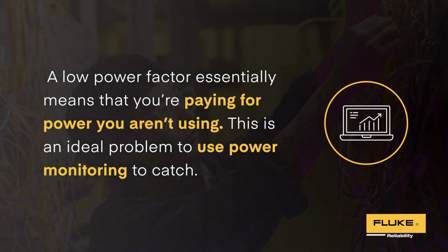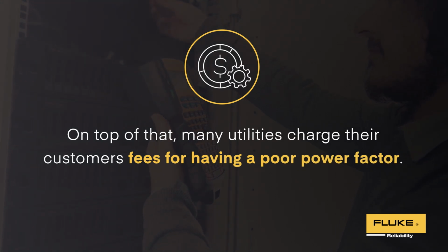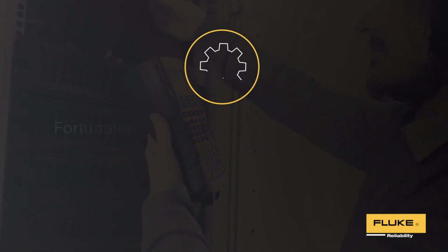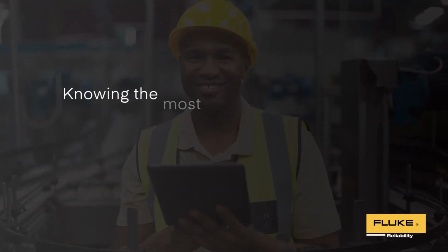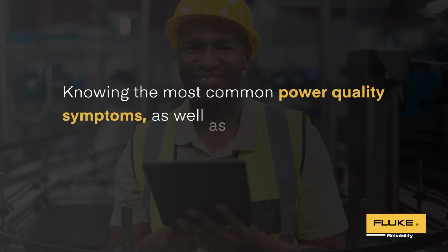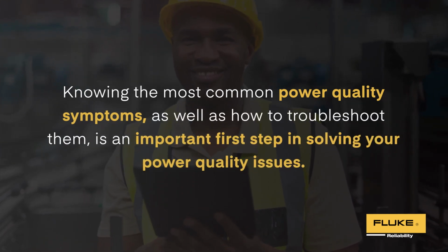This is an ideal problem to use power monitoring to catch. On top of that, many utilities charge their customers fees for having poor power factor. A power factor below 85% is wasteful and can indicate loading problems. Fortunately, this can be relatively easy to fix. Knowing the most common power quality symptoms as well as how to troubleshoot them is an important first step in solving your power quality issues.